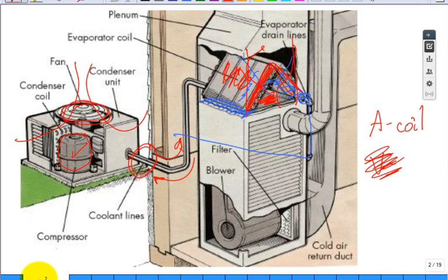So you go back to this and you say, the large line, is it carrying fluid vapor into the house or fluid vapor out of the house? Which way is the large line fluid going? And people will get this all messed up. They really will. So it's actually the suction line is the larger diameter. It's insulated and it's carrying vapor after or from the evaporator back out of the house to the compressor. That's confusing to a lot of people. And the smaller diameter, bare, typically not insulated, is the liquid line. And it's carrying it after the condenser. It's saturated liquid, typically out of the condenser, high pressure up into the house. And it's going to the expansion valve, feed the expansion valve.